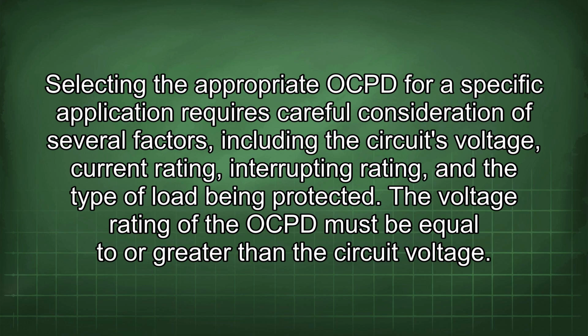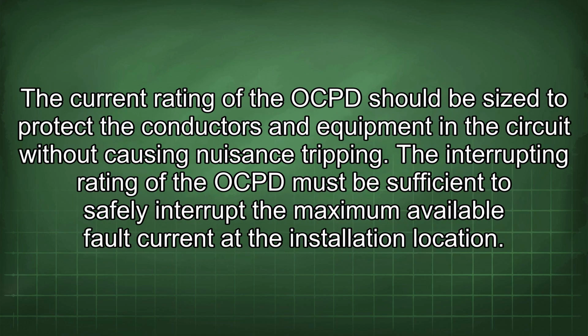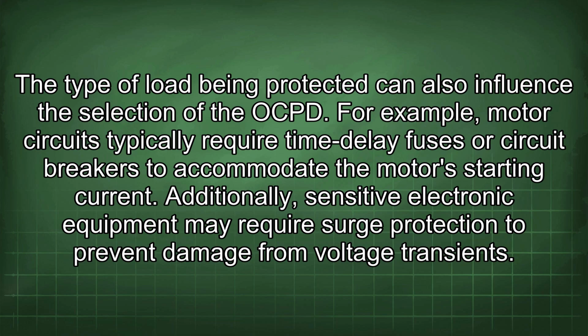The voltage rating of the OCPD must be equal to or greater than the circuit voltage. The current rating of the OCPD should be sized to protect the conductors and equipment in the circuit without causing nuisance tripping. The interrupting rating of the OCPD must be sufficient to safely interrupt the maximum available fault current at the installation location. The type of load being protected can also influence the selection of the OCPD.